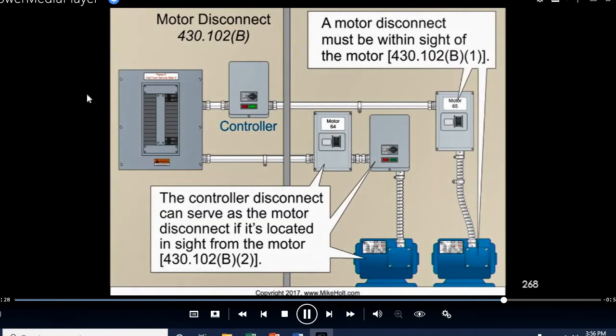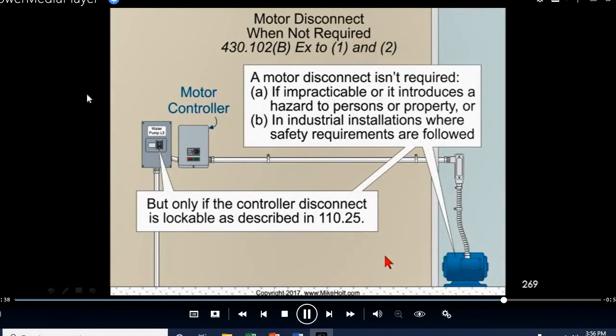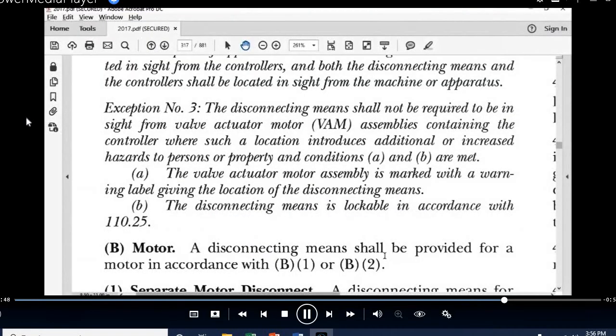Now let's go with the motor. The disconnect for the motor must be within sight of the motor, or you can use the disconnect for the controller if it's within sight of the motor. Now there is a provision to not have a disconnect within sight of the motor. That's a good way to do it, but take a look at this real strange rule.